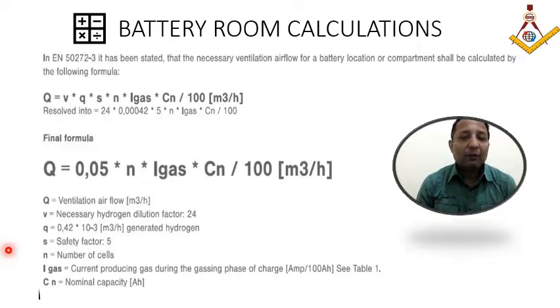And if you see this formula carefully, this is a formula which has been applied to calculate the ventilation rate to take out the hazardous gas outside. But again, there is one more thing over here. Normally, this or 12 air changes, which is standard industrial practice, whichever is higher, is taken into consideration while designing the battery room system. The battery room being a hazardous area, any electrical equipment which is kept inside, for example a fan or panel, you need to consider that the fan has to be suitable for zone 1, gas group 2C, temperature class T3. So this I am going to cover in detail. Fan cost is also significantly higher in the battery room, and the details I will cover in a subsequent session.